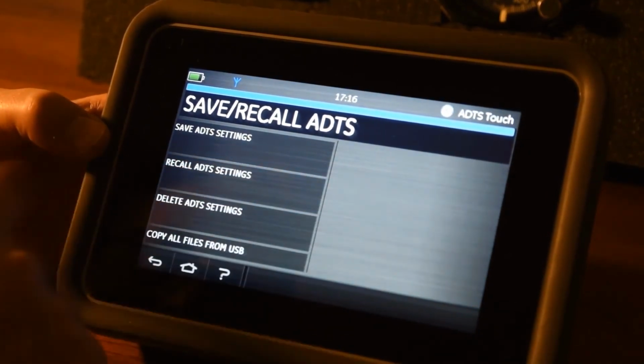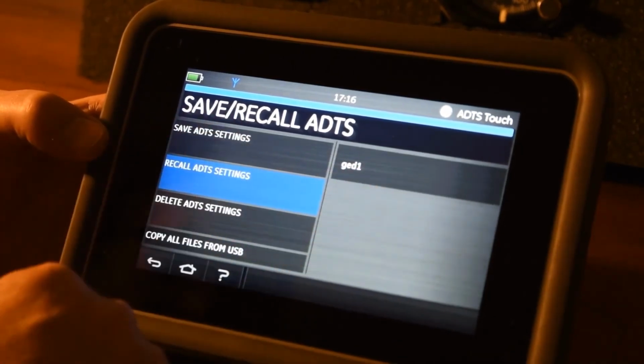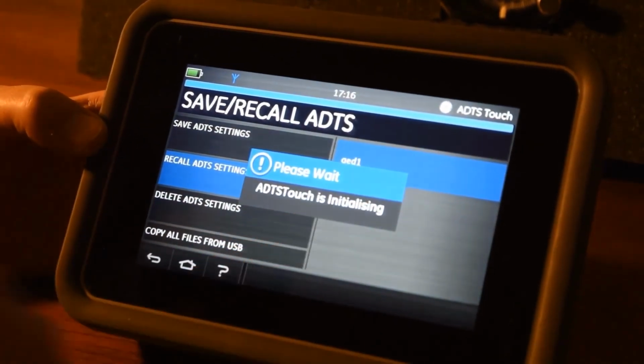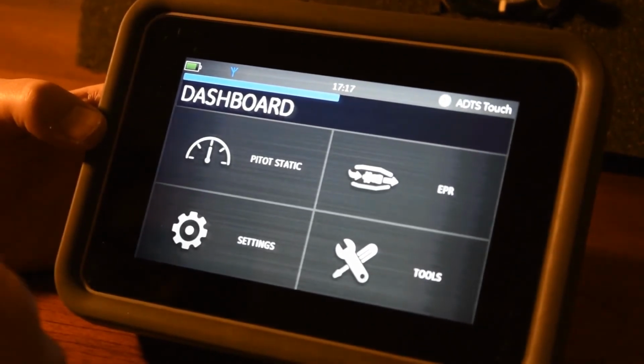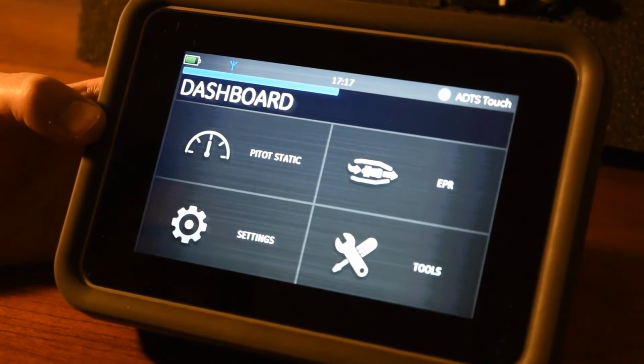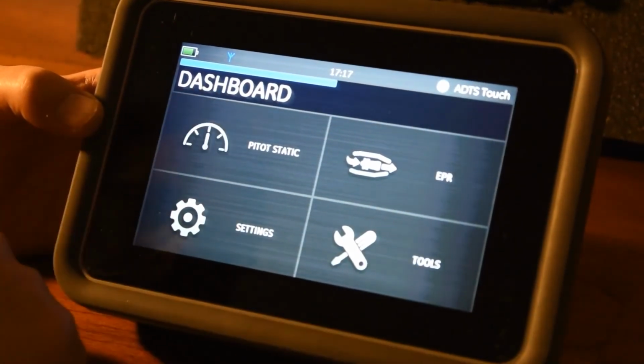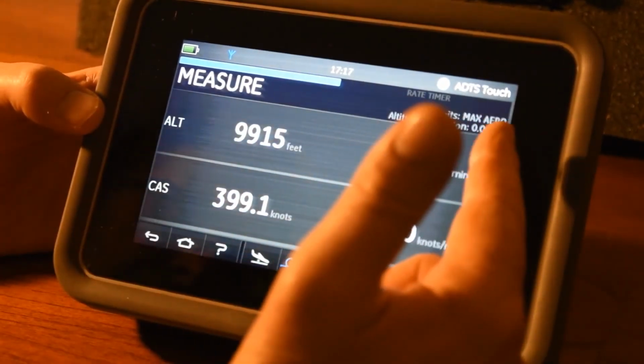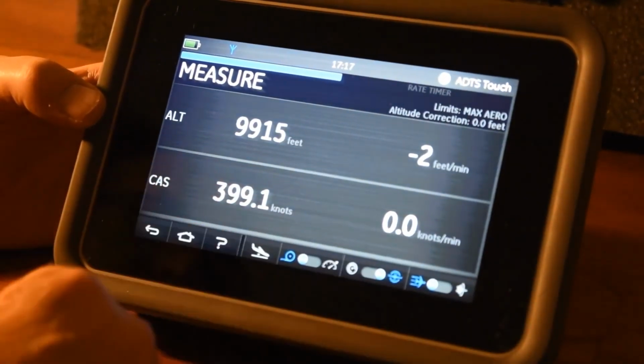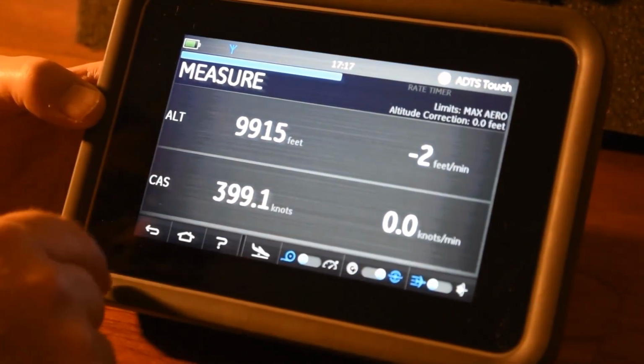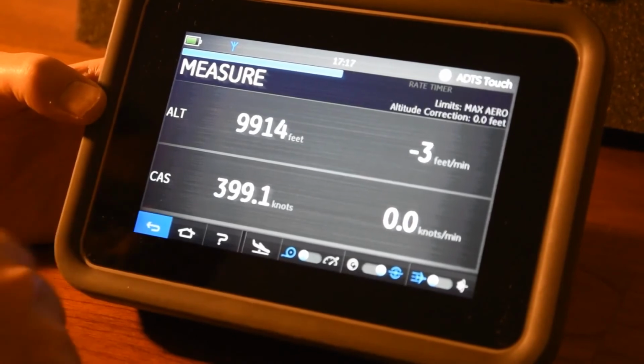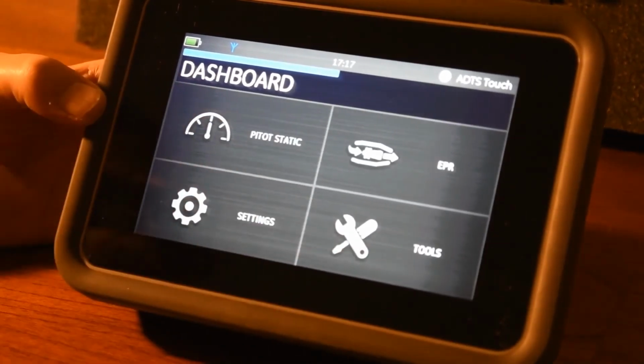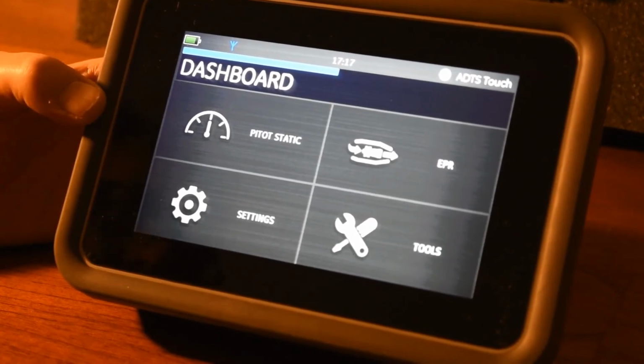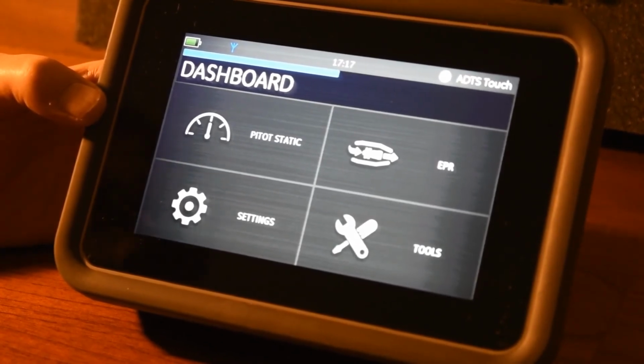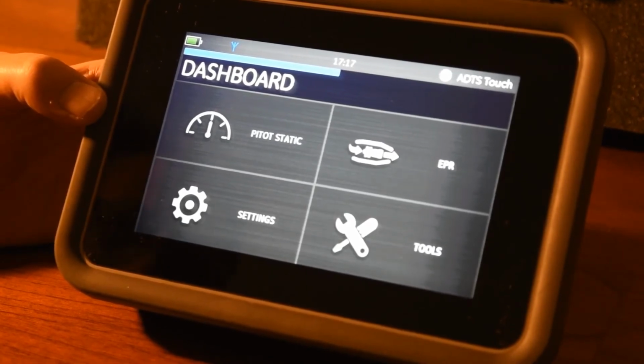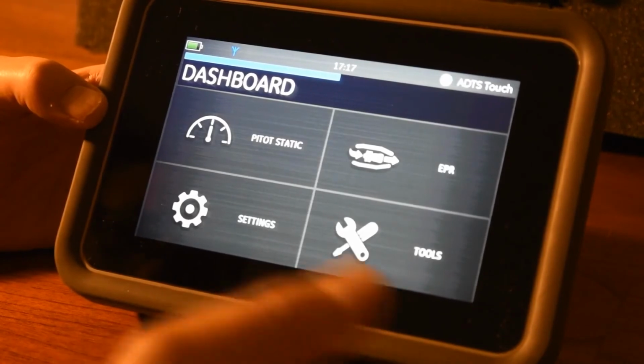Once I've saved it, all I need to do is recall it. So this one here called JED1, I hit that and it says, hang on a minute, I'm going to set the whole ADTS touch into what those settings were when you last set it up, and save that as parameters. So I was in helicopter mode, now I'm back in max aero, so everything has gone back to the settings I'd saved against my name for that test. It just personalizes it and saves time having to go in. Again, you've got altitude correction if you put that in for a particular aircraft, and you've edited limits, etc. So you don't want to do that every time. So just save it against your name.